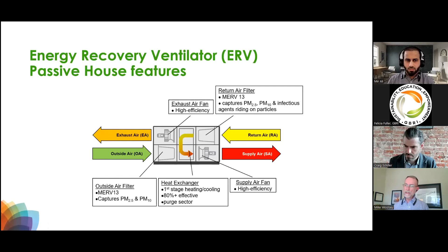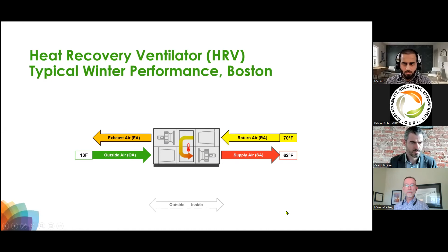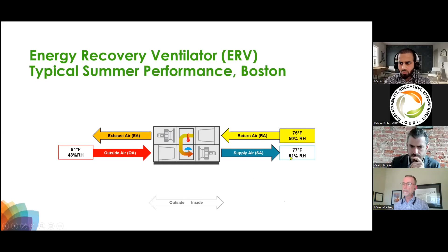So what does this look like? If you're in Boston, and I know some of you are, on a design day, it's 13 degrees outside, and an HRV will take waste heat coming out of the building at 70 degrees and heat up the heat exchanger, which heats up the outside air all the way up to 62 degrees. That's already a pretty comfortable level that might be warm enough, depending on how occupied the building is. If it's not, then we simply add some post-heating and post-cooling. Similarly, we see that we can also control humidity with an ERV by taking moisture leaving the building and returning it to the supply airstream. And then finally, and quickly, don't overlook that energy recovery works pretty well in the summer months too, because it rejects heat and moisture from outdoors so that you never have to deal with it downstream. So in this case, when it's 91 degrees out, 43% relative humidity, the air is cooled all the way down to 77, and the moisture level is just about neutral for these conditions.